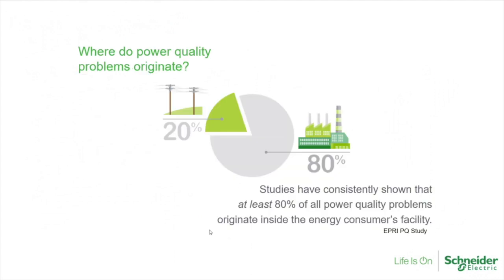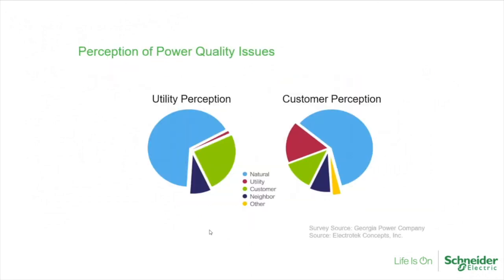So where do power quality problems originate? I assume that a lot of the people on the call today are probably in utilities, and EPRI did a study in the past that shows that consistently about 80% of power quality problems come from the consumer's facility rather than the utility. But they also did a survey at the time to get what customers and utilities perceive power quality events as, which is kind of interesting because utilities think it's either natural or largely caused by a customer, and the customer's perception is either that it's natural, and then their next biggest chunk is that it's the utility that's at fault.